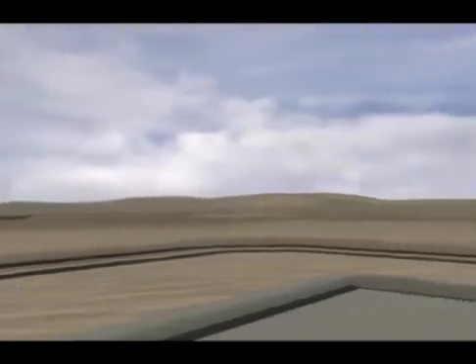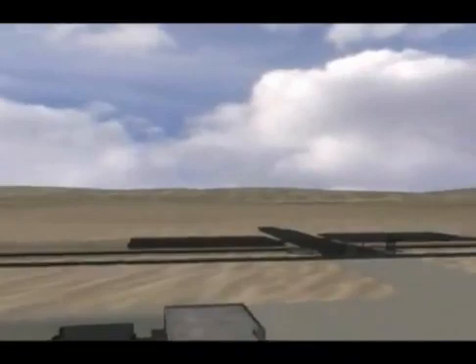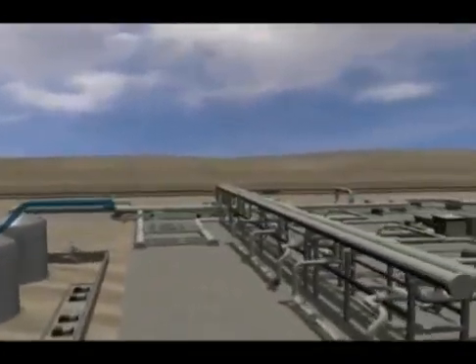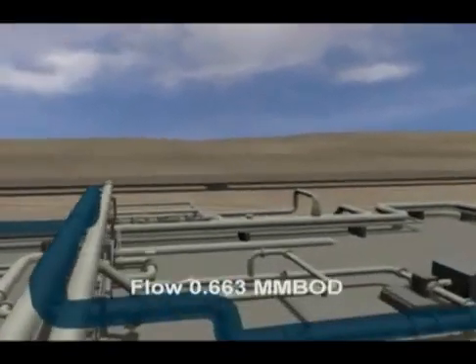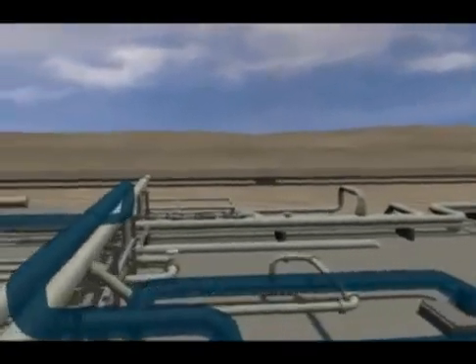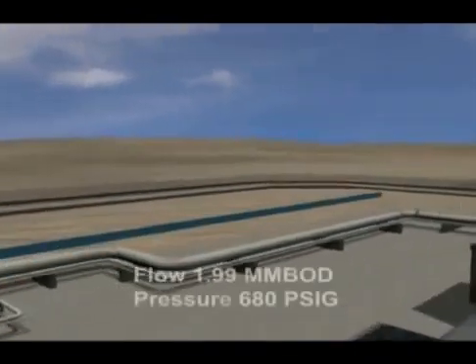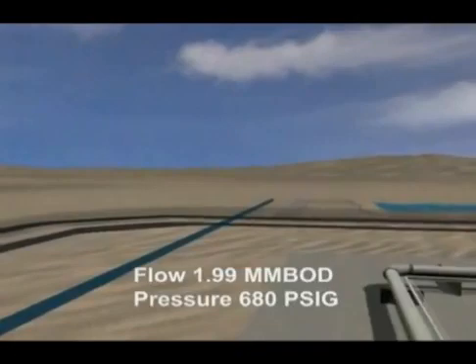The project will also upgrade the DCS system, install a new air system, and upgrade various existing booster pump components. The Haradh Water Injection Plant will also pressurize 1.99 million barrels per day from 260 to 680 PSIG in order to transport the treated water to the Harad plant.